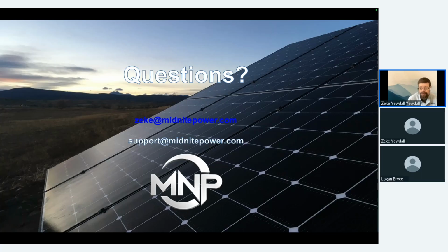And also on your battery, we never used to put lightning protection on the 48 volt of the battery because lead acid batteries were a gigantic surge suppressor. You couldn't change their voltage very quickly. Lithium batteries, the actual batteries still perform that way, but we're not connected to the actual battery cells. We are connected through a BMS, which means those battery cells are no longer protecting the DC input of the inverter or the BMS from surges on that DC line between the battery and the inverter. Now, it's usually a really short cable, 5 feet sometimes, maybe 10 feet. But if you're really concerned about lightning in a lightning prone area, putting a DC surge suppressor on that battery 48 volts DC would also be recommended.